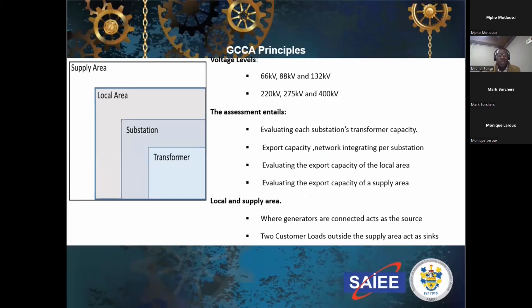We have to use the GCCA principles and explain how it was developed. First we look at the voltage levels: is it 66 kV, 88 kV, which is distribution, up to 132 for transmission? Is it 220, 275, or 400 kV? Lately, because of the sizes we're getting, we'll be talking at 765 kV, and soon maybe HVDC, because the quantums we're getting are 1,300 megawatts. Lately it's standard to get 540 megawatts of PV in the Northern Cape.